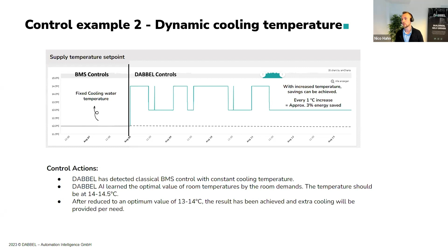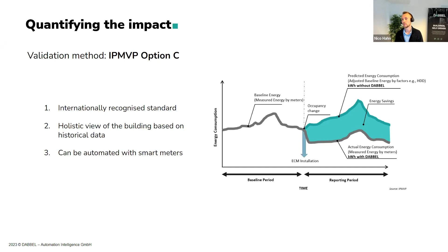This enables us to achieve tremendous results, which we can then prove in a statistically verified way, using a benchmark, a baseline developed for this particular building. We take energy consumption from the past, cleanse the data, take out heating degree days, weather, cooling degree days, and eventually occupancy—we've all been through COVID, with less occupancy in most buildings. This gives us an objective baseline where we can compare actual energy consumption, read monthly, and clearly quantify and verify savings achieved by the software.